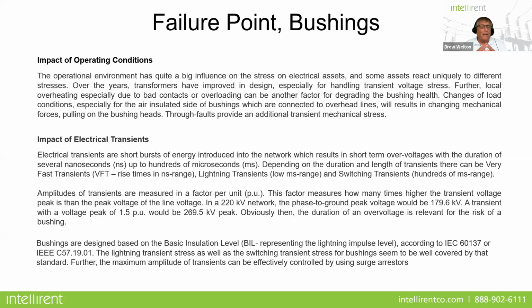So if we look at the impact of operating conditions, your operational environment has quite a lot of influence over stress on these electrical assets, and some react differently to different stresses. But over the years, transformers have improved in design. We know that. Let's talk about transient voltages or through faults. We know that certain types of transformers can handle transients better than others, core form versus shell form.